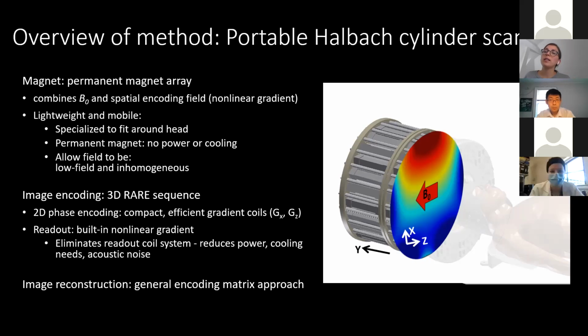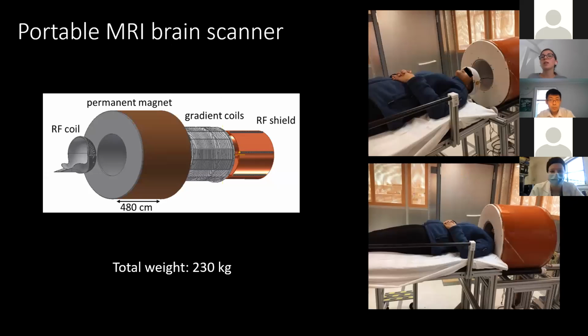Finally, because we have this nonlinear field, we use a special image reconstruction method that uses a general encoding matrix approach to reconstruct the images, as opposed to the traditional FFT approach. So here's a drawing of our system components, as well as some photos on the right. The total system weight is 230 kilograms, so it's very lightweight compared to traditional scanners, and you can see it's also very compact. The main scanner components are the RF coil, the permanent magnet, the gradient coils, and then the RF shield. I'll be talking about each of these components a little bit more.